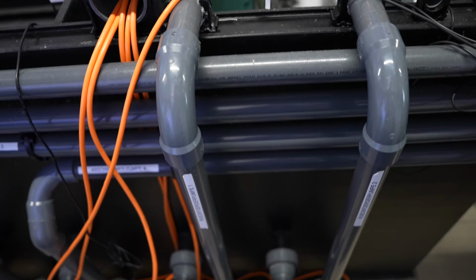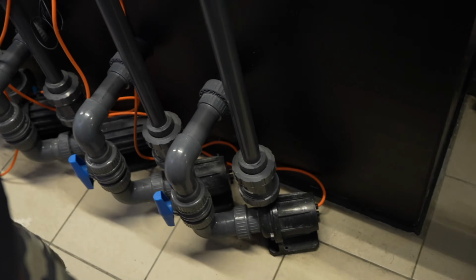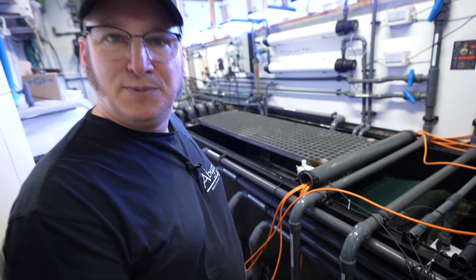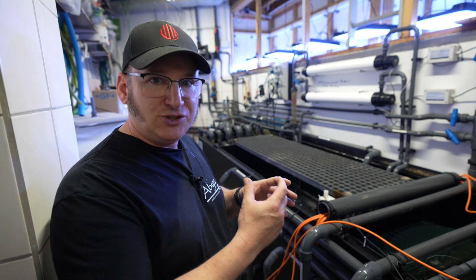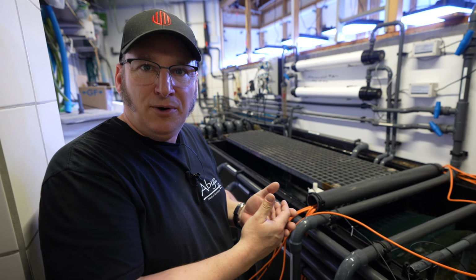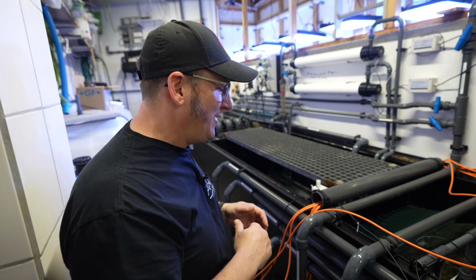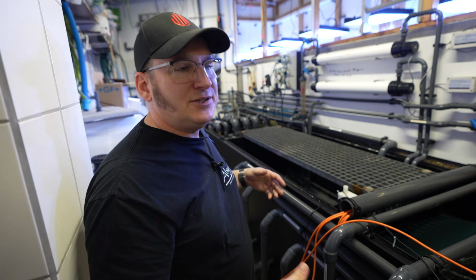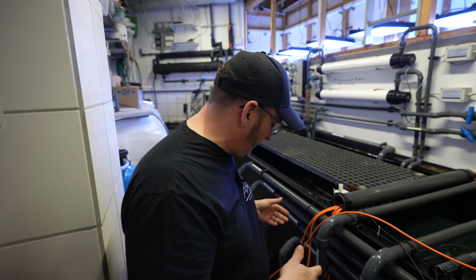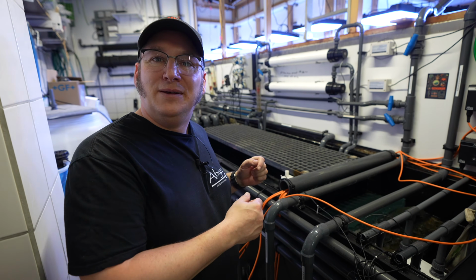Yeah. No larger issues. I mean, you need to clean the pumps, obviously, as with any technical things, but the noise you hear, by the way, are the security valves on the pump. So this is actually what's really wearing out. Just because of the speed that the water is moving through the check valve, the valve wears out, and then at some point it won't close anymore, and then it starts making this noise. So I'm just saying this is not the pump noise that you're hearing. But it's not that loud, we have to say that.